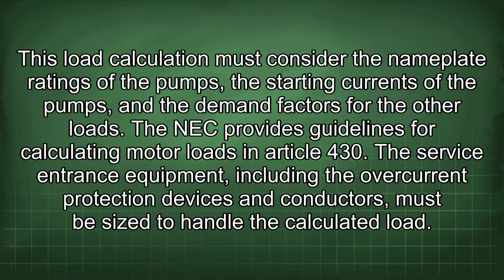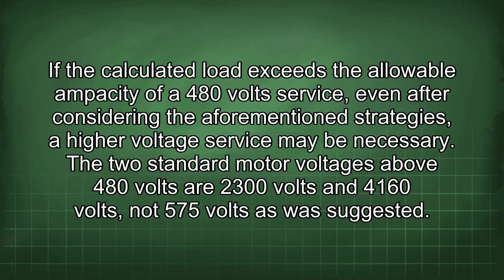This load calculation must consider the nameplate ratings of the pumps, the starting currents of the pumps, and the demand factors for the other loads. The NEC provides guidelines for calculating motor loads in Article 430. The service entrance equipment, including the overcurrent protection devices and conductors, must be sized to handle the calculated load. If the calculated load exceeds the allowable ampacity of a 480 volt service, even after considering the aforementioned strategies, a high voltage service may be necessary.